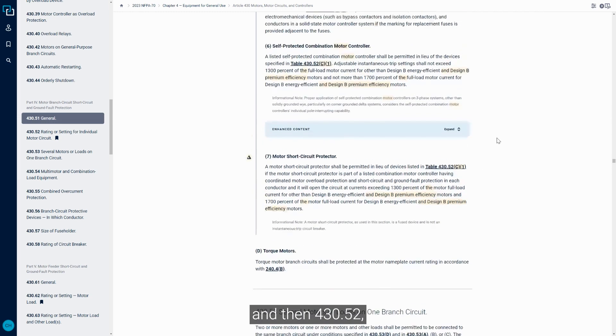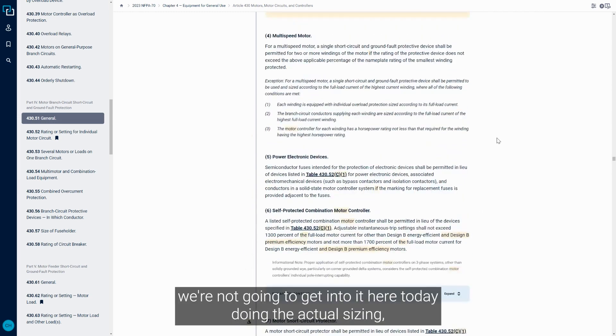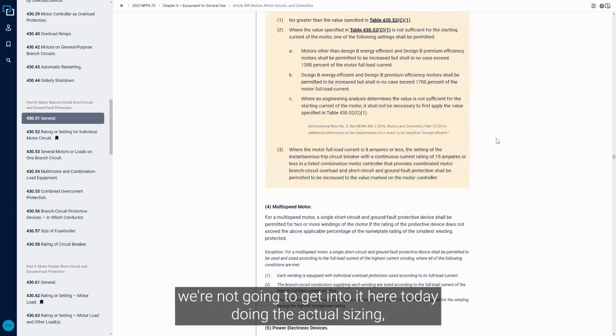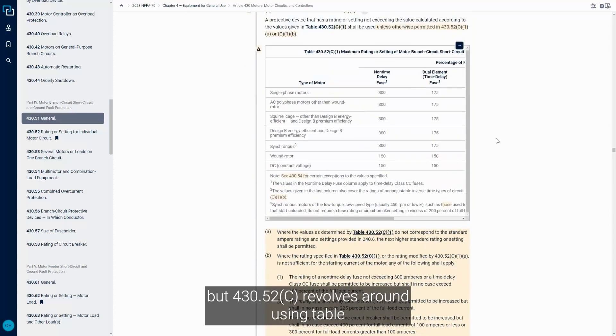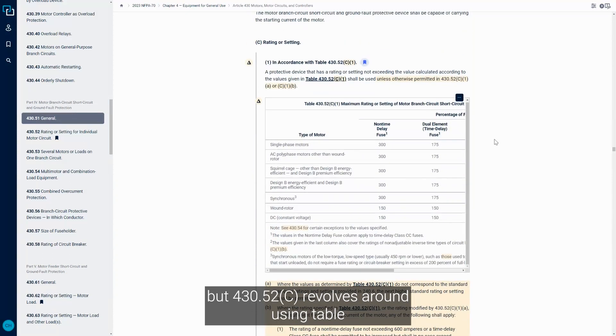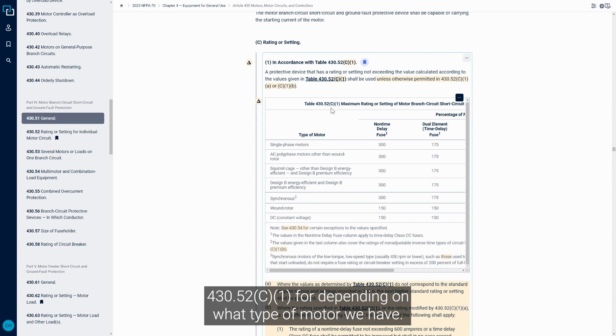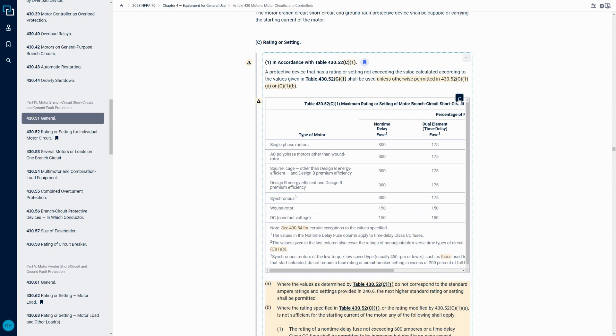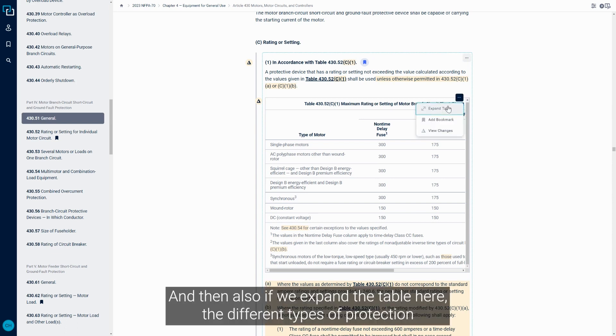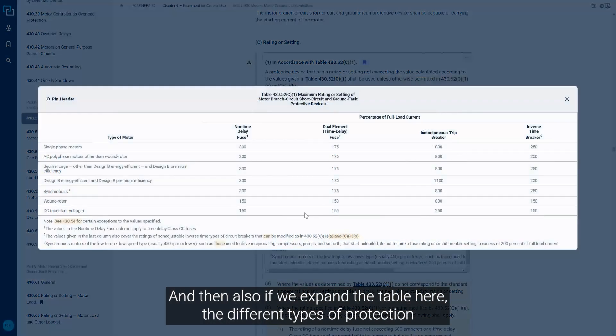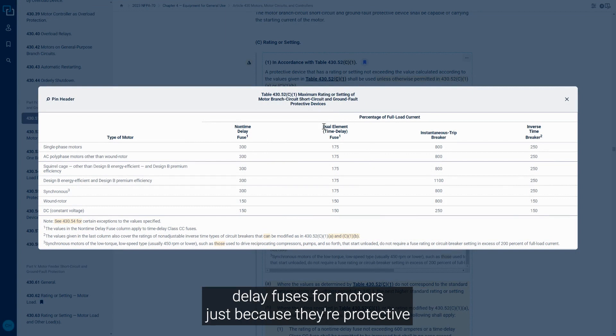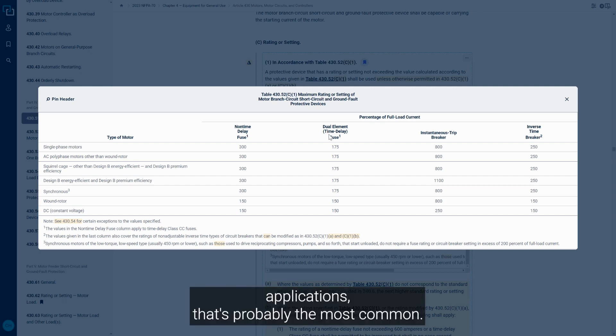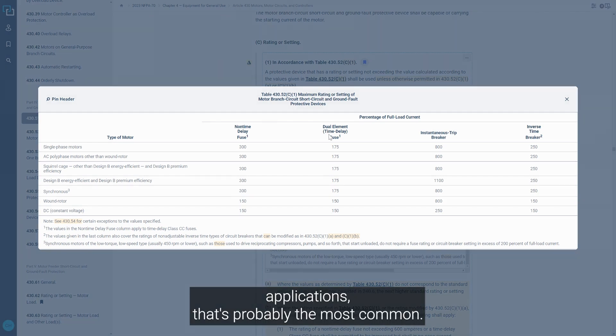We're not going to get into the actual sizing here today, but 430.52C revolves around using table 430.52C1 depending on what type of motor we have. If we expand the table, we see the different types of protection that could be utilized. Very commonly, it ends up being dual element time delay fuses for motors just because of their protective applications.